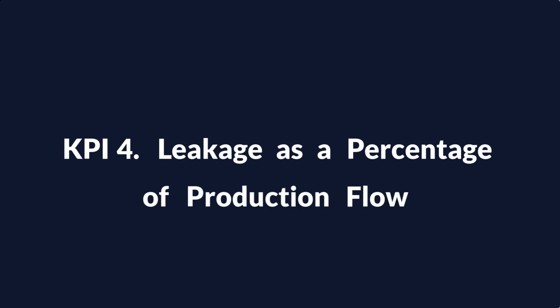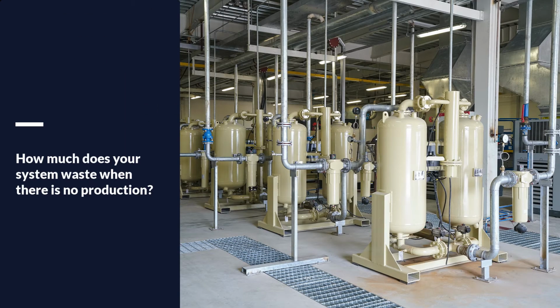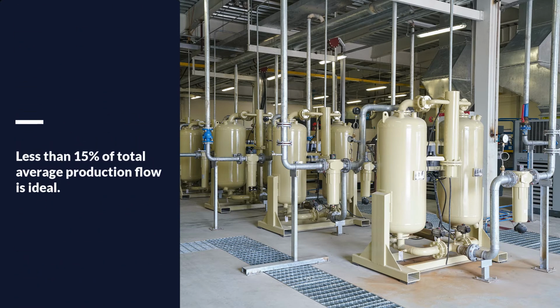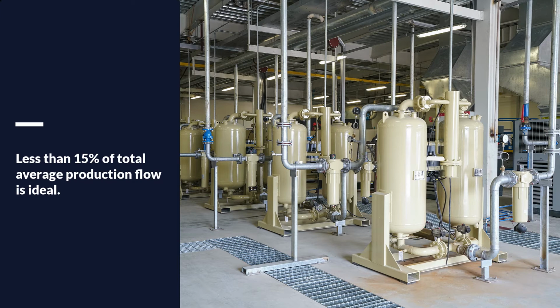KPI 4. Leakage as a percentage of production flow. This KPI is a measure of how much system waste occurs during times of no production and is expressed as a proportion of total flow. This measurement is easy to calculate in a shift-oriented plant or during periods of planned downtime. It is more difficult to measure at locations where production never shuts down. A good number for this indicator is less than 15% of production average flow. If you discover that the air waste in your system is more than 15% of the total flow, then some leakage detection and repair work will be required.